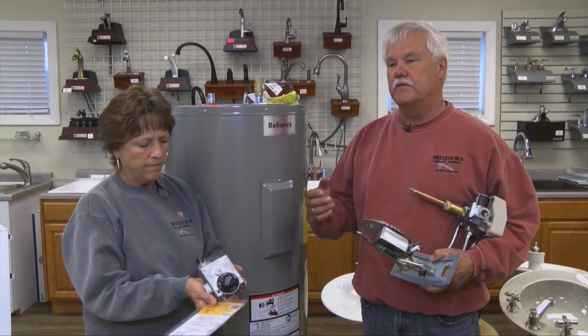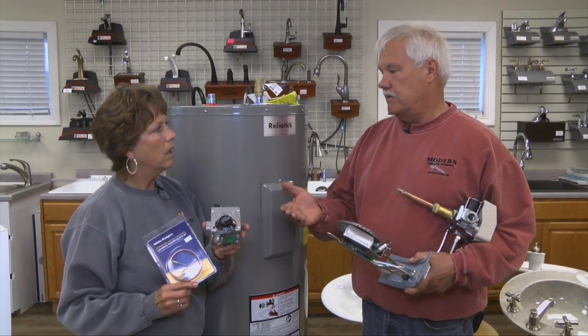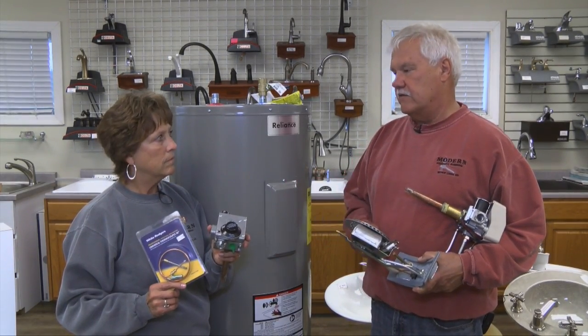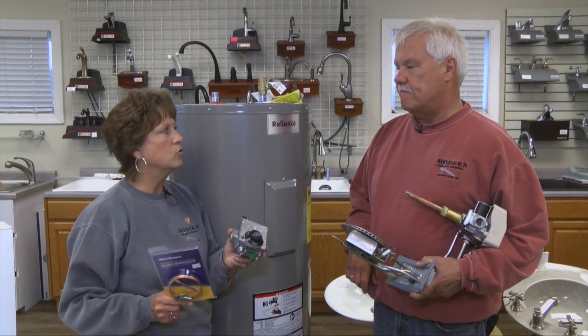Well, if you're going to measure it — like if we do a home care study where there's a home child care — then it can be a maximum of 120 degrees. But a lot of people like their water heater at 125 or 130. If it's mandated, it has to be 120 or less.